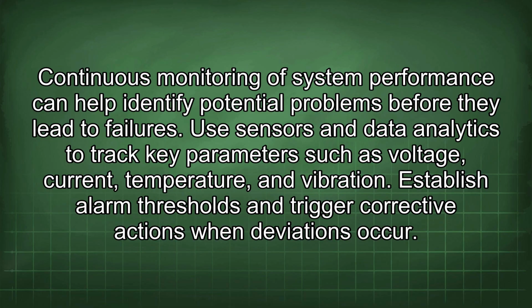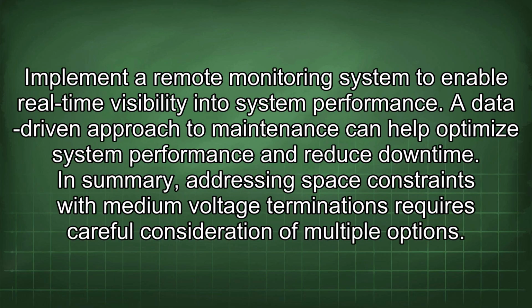Continuous monitoring of system performance can help identify potential problems before they lead to failures. Use sensors and data analytics to track key parameters such as voltage, current, temperature, and vibration. Establish alarm thresholds and trigger corrective actions when deviations occur. Implement a remote monitoring system to enable real-time visibility into system performance. A data-driven approach to maintenance can help optimize system performance and reduce downtime.